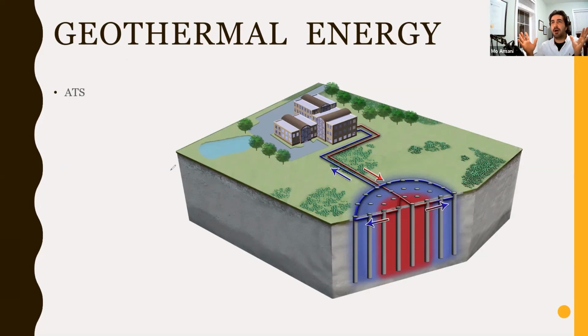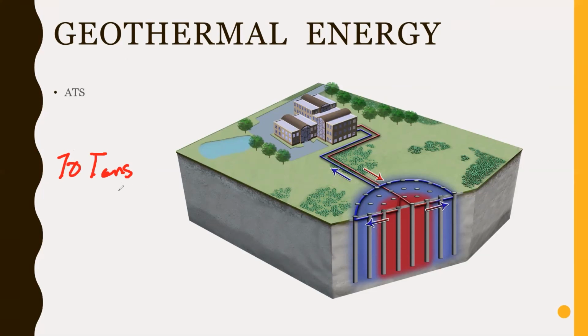Peter, just a rough estimation for that 10-ton cooling load, how much is the investment for that? If you do the math and save, let's say, $5,000 on hot water and free cooling, your capital cost will be no more than $15,000 or $20,000. This gives you a 3-year payback period. If you want to bring it down to kilowatts, 10 tons is 120,000 BTU divided by 3,415, which gives you the number of kilowatts. You could work with those numbers.